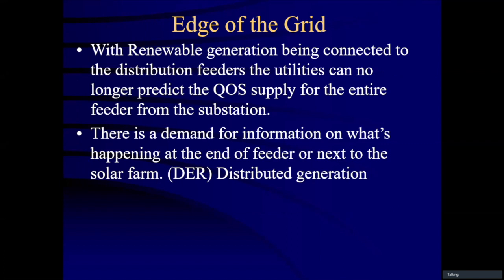There's another term for this, and we call this edge of the grid. That edge of the grid was pioneered by EPRI to move the knowledge base of power quality from the distribution feeders in the substation to the end of the feeder. And the end of the feeder is not as simple, because the feeders are not all just one long line. There are many branches and different configurations.